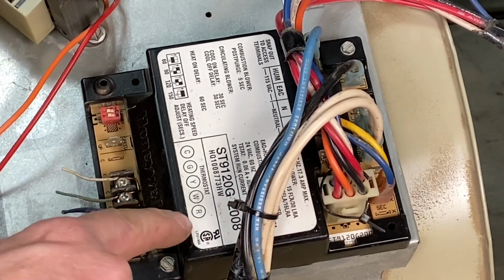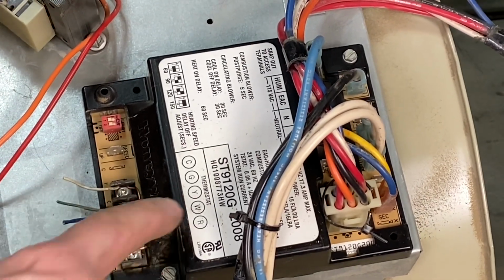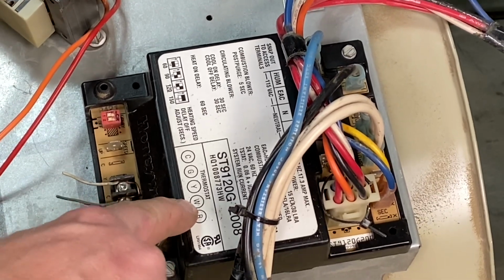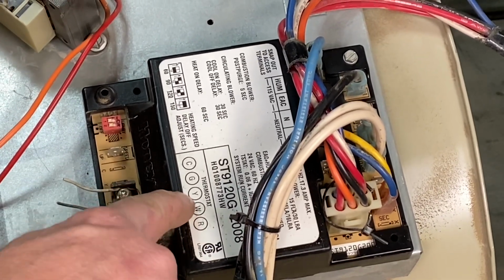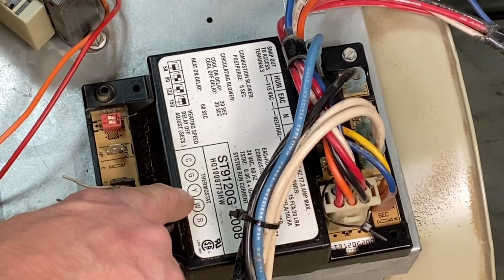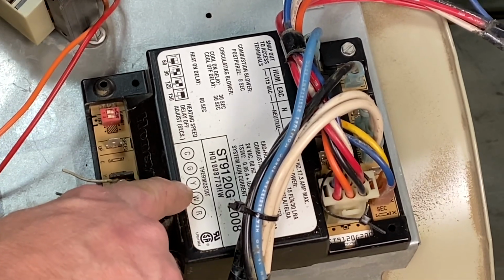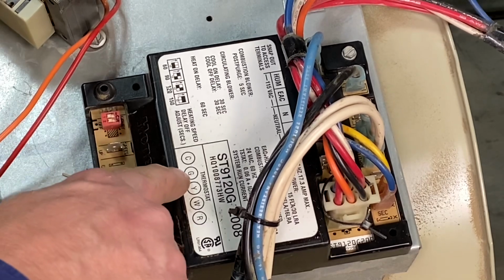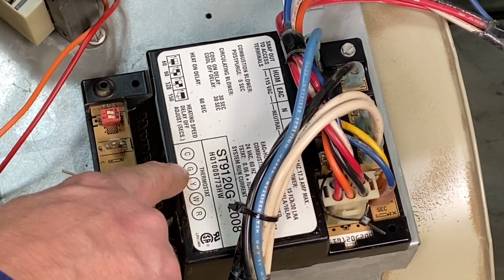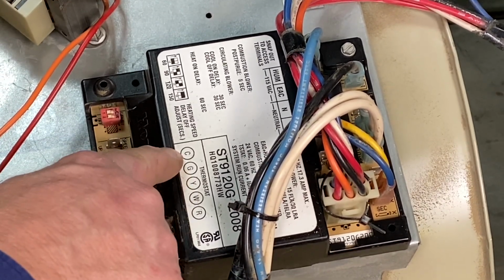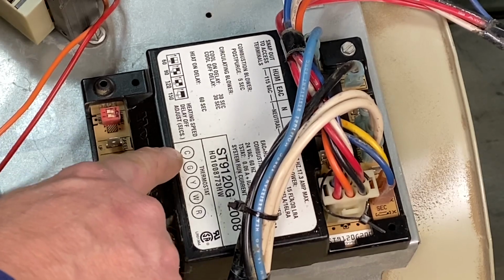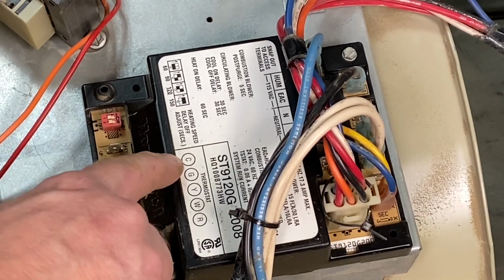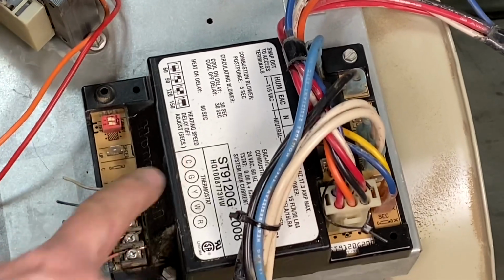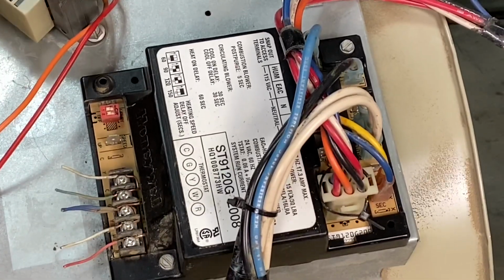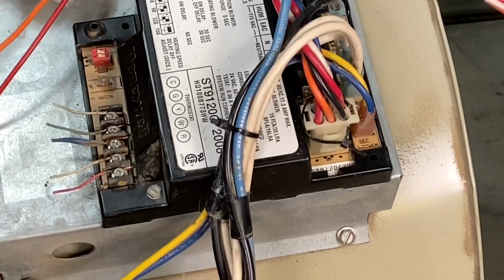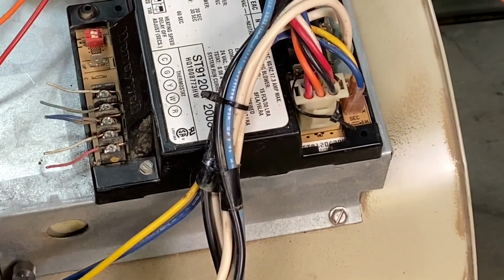Make sure you connect R from this unit to R at the thermostat. Make sure W from the unit connects to W at the thermostat. Make sure Y from the thermostat connects to this Y terminal and also connects to the Y terminal at the compressor contactor outside. The G terminal goes to the G terminal of the thermostat, and the C terminal goes to the C terminal of the thermostat and the common side of the compressor contactor outside. So now that we've got those wires separate, we can undo these 4 screws.